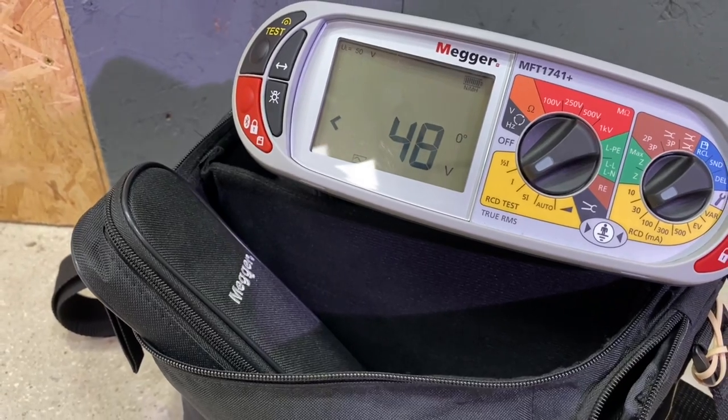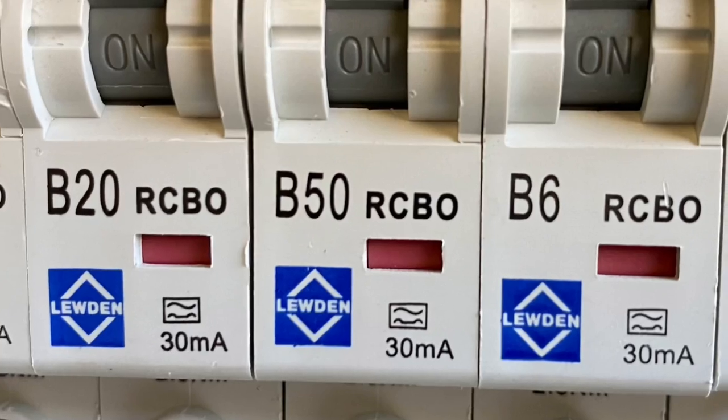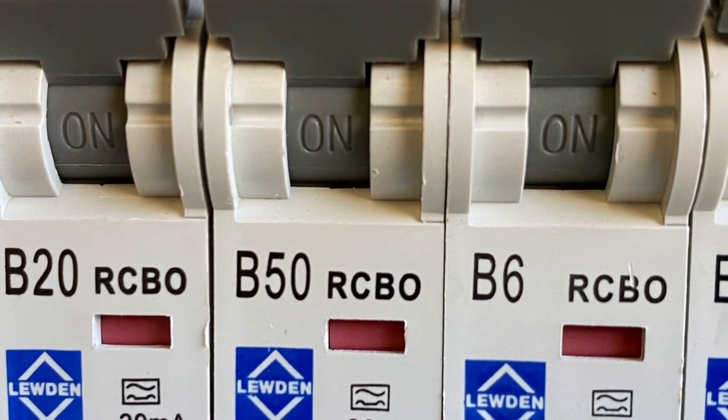When we're thinking about those times — are those times relevant to all types? I would say those times are relevant to all of the types, because BS 7671 doesn't make a distinction. There's nowhere in there that makes that distinction. On the A-type devices, it's an AC-type breaker and an A-type breaker rolled into one, so the two characteristics are different to each other in terms of how they're tested — according to the 61008 manufacturing standard.